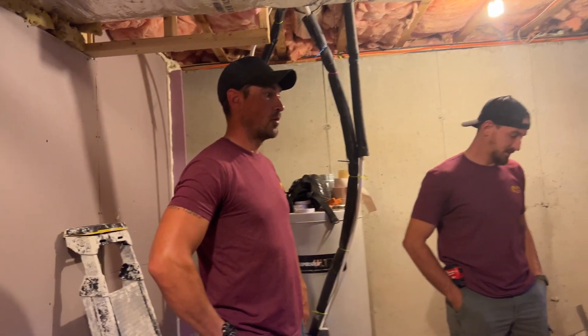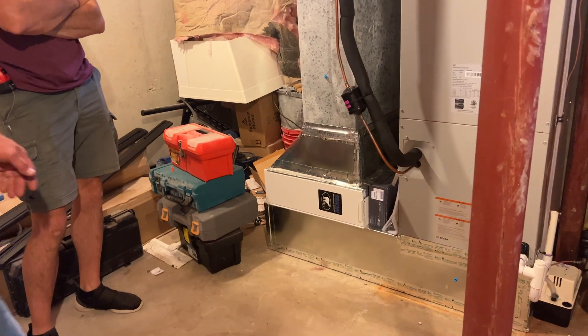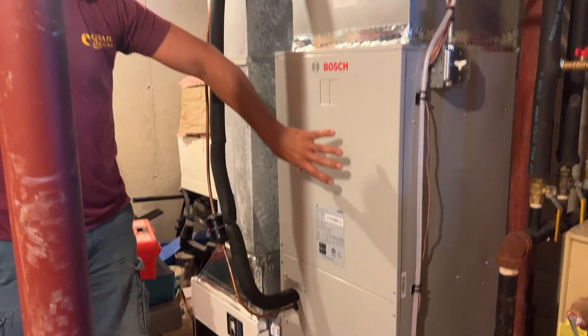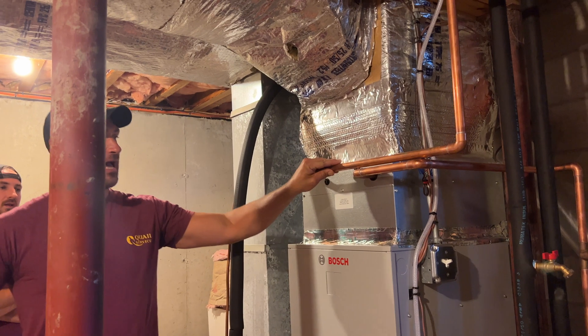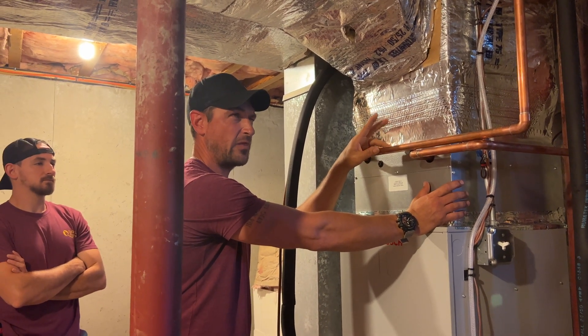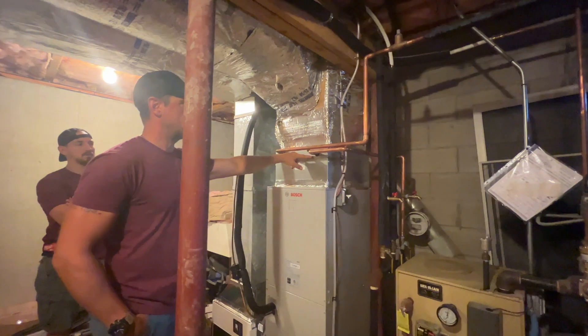James, do you want to describe what these components are? I literally thought changing the AC was just about changing the condensers outside. You can do that if you're keeping the indoor unit, but no. So you've got your five-inch pleated Merv 8 high-efficiency filter — good for about six to nine months. This is the air handler. Down here is the evaporator coil; refrigerant comes from the condenser in through here. There's a fan motor in here blowing all the cool air — or hot air in heating season — up through here. This is the hydronic coil, which is your auxiliary heat. Heat pumps lose efficiency when temperatures drop below freezing, but Bosch maintains 100% capacity down to about 13 degrees outside. Since you have your boiler and an existing hydronic system, we put in this external hydronic heating coil tied into your boiler.